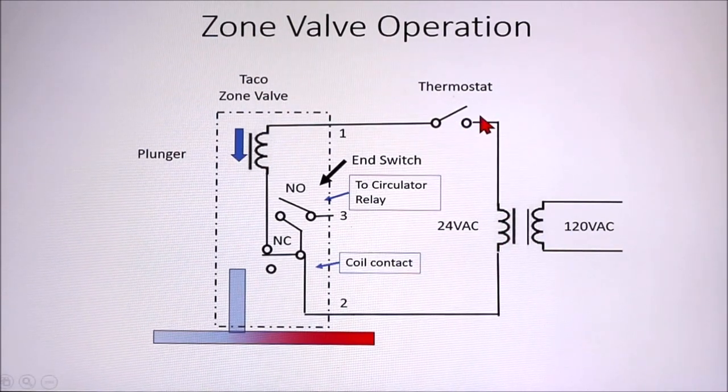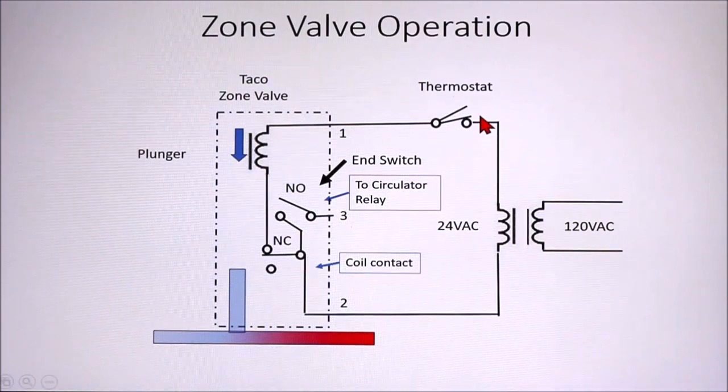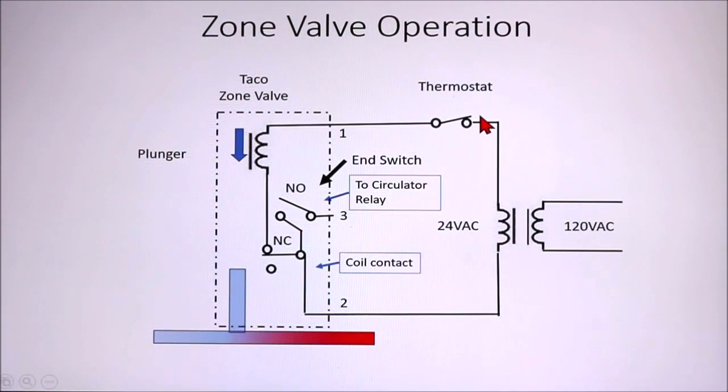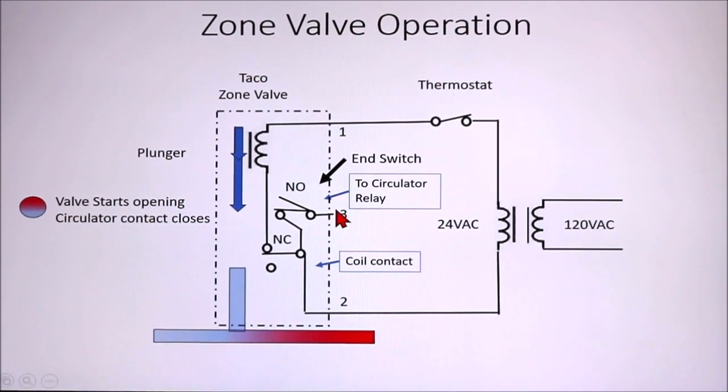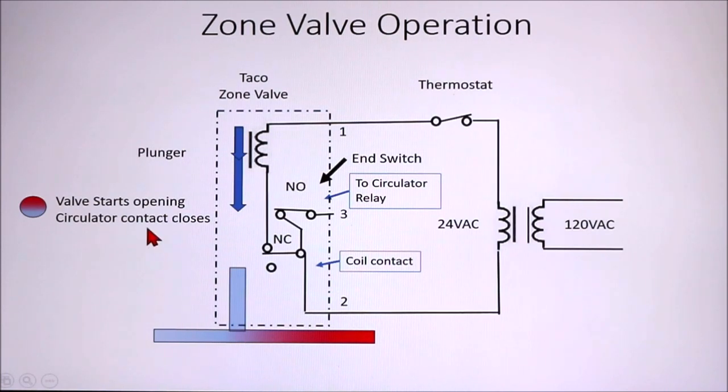So the first thing that happens is when the thermostat calls for heat, it closes like that. That allows current to flow through the coil of the zone valve, heat up the wax, and start moving the plunger. That happens, and at the same time, the circulator relay contact closes, and the valve starts opening. It starts to push on this part of the valve, which begins the circulation of hot water.